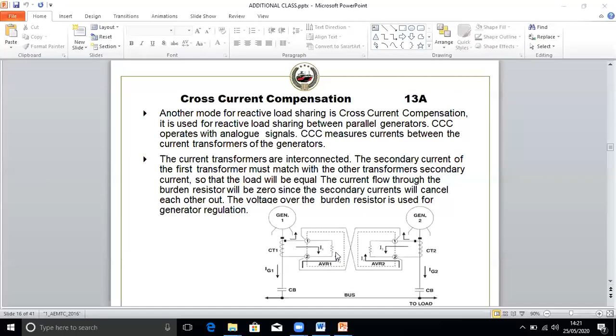Whenever there is a difference in this current, it will give more excitation, because this is inside the AVR circuit. So the current flow through the burden resistor will be 0. This is the burden resistor. This burden resistor current will be 0 when both are sharing equal current. Whenever there is a difference, this burden resistor output voltage will vary and it will give the correction inside the AVR. This is called cross current compensation.